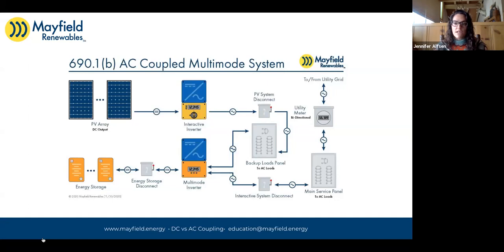So the grid-tied inverter, or what we're calling the interactive inverter—if the interactive inverter is in the garage into a sub panel fed by the main in the basement, and then with proper switch gear, putting the multi-mode inverter and battery in the basement, feeding backup loads.